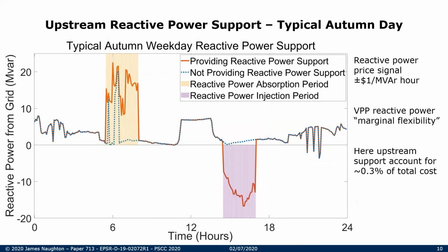This graph shows the reactive power output of the VPP in the case where upstream reactive power support is requested versus when it isn't. In this case, it was considered that a price signal was provided to the VPP to incentivize injection or absorption of reactive power rather than requesting a specific amount. This is why the reactive power injection or absorption is not constant over the periods where the support was requested. The price provided to the VPP was plus minus $1 per MVAr hour, which acts to show how much flexibility the VPP has with limited impact on its economic performance. To put it in perspective, the VPP accrued about $70 for its upstream reactive power support, which is about 0.3% of the objective function.